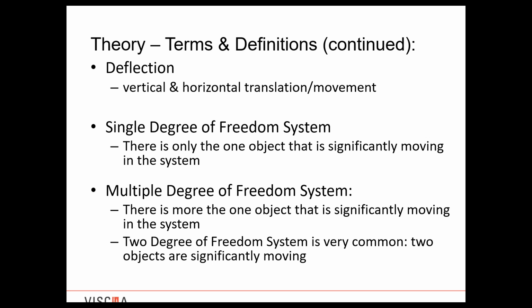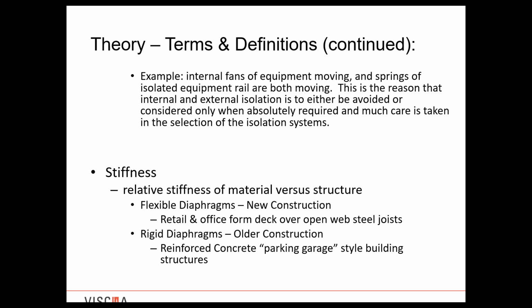Now, when you have a multiple degree of freedom system, there is more than one object that is significantly moving in the system. So an example of this, we'll see on the next slide, but this example is a 2 degree of freedom system, which is very common. 2 degrees, 2 masses of equipment are moving. So in this example, you have an internal fan of equipment moving. The springs of the isolated equipment are both moving. So if you can think back to that nice illustration that John had up with the 4 different types of spring isolator restraints, if you had a curb down in that bottom lower left hand that had springs in it, that curb would be deflecting as well as your equipment is also moving.